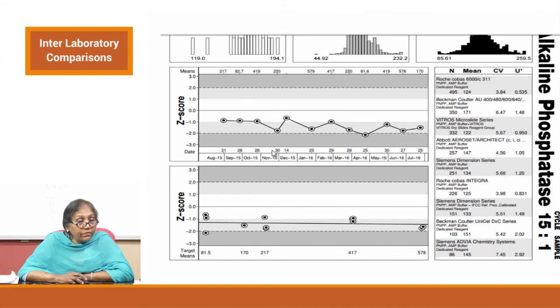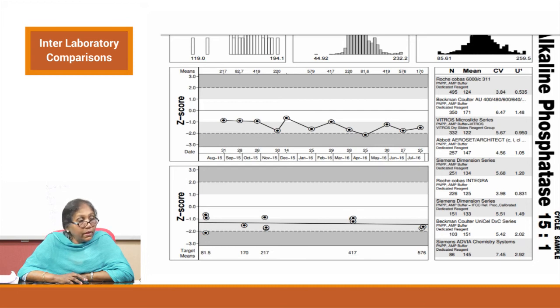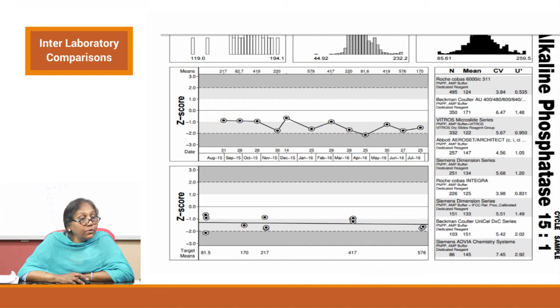This alkaline phosphatase example shows everything on the lower side with no corrective actions taken — only one violation noticed, yet the SDI scores have been sitting below zero and not been attended to. There is another analyte that has not yet hit the 2 SD line but is almost there, and then crosses it with still no corrective action. This is how EQAS is not adequately used or is misused.